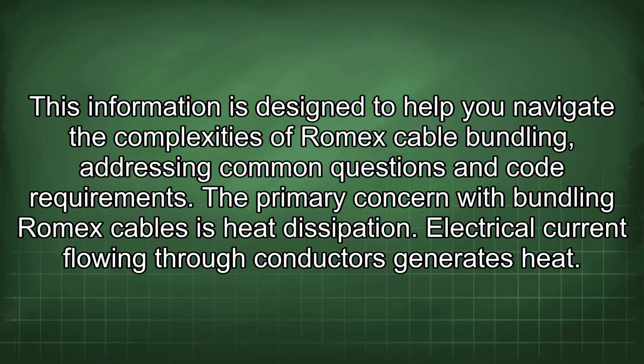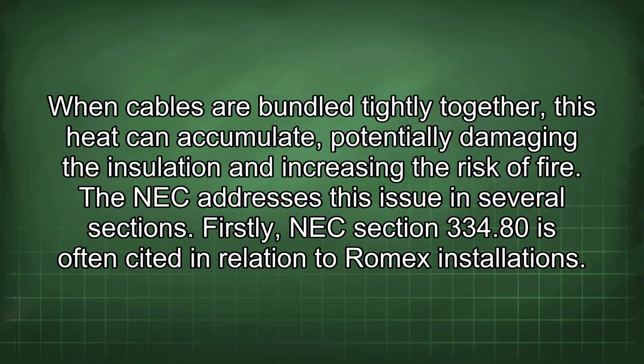The primary concern with bundling Romex cables is heat dissipation. Electrical current flowing through conductors generates heat. When cables are bundled tightly together, this heat can accumulate, potentially damaging the insulation and increasing the risk of fire. The NEC addresses this issue in several sections.